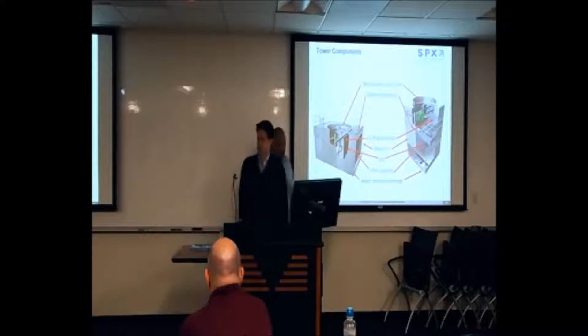All right, thanks, Larry. So what we're going to do today is go through a couple of the tower components for those of you who may not have been on towers much in the past, and then after that we'll dive into some maintenance features and things to consider when you're on and around these towers. So real quickly, the towers specifically that you guys received recently was this cross-flow tower on the left. As Aaron mentioned, you have an open cooling tower, and within open cooling towers you have cross-flow towers and you have counterflow towers. So cross-flow is this one on the left. That is when the air is traveling across the direction of the water. So, and I'll explain this in the components, but water is falling down the tower and air is traveling across the direction of the water travel.